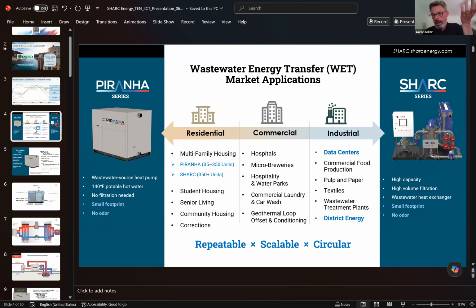Whereas the piranha makes the domestic hot water directly, the shark across the street is making the energy for the process loop that then runs into a Colmac heat pump, in this case, to make the hot water. So we're providing that condenser water for the heat pumps that do the heating, cooling, and hot water production for the building. So again, we can support direct hot water production or indirect in a multifamily residential building, and we've got it proven all over the place. Perfect. And again, rule of thumb, you put that piranha in, and if you can capture all the wastewater before it leaves the building, like that final black pipe, the piranha can make 91% of the hot water for the building.